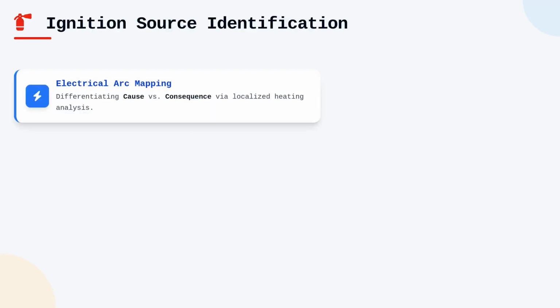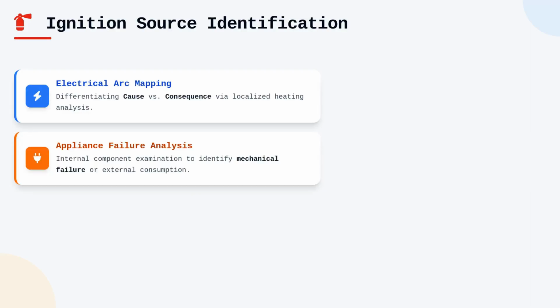The identification of an ignition source demands a methodical, exhaustive approach to eliminate all potential accidental or natural causes. When we examine electrical arc mapping, we look for physical evidence of localized heating on conductors, which helps differentiate between arcing as a cause of the fire versus arcing as a consequence of fire heating. Appliance failure analysis involves examining internal components to determine if a mechanical or electrical failure occurred within the device or if it was merely consumed by external fire growth.